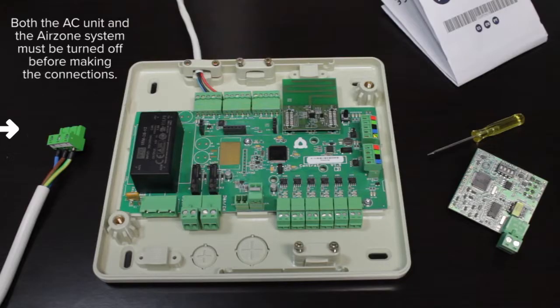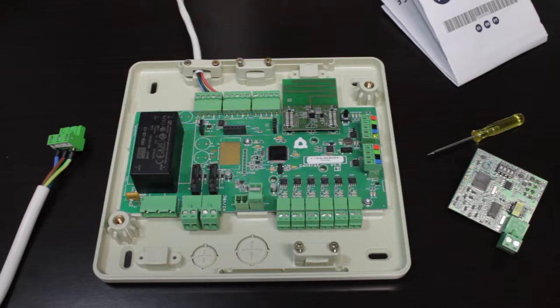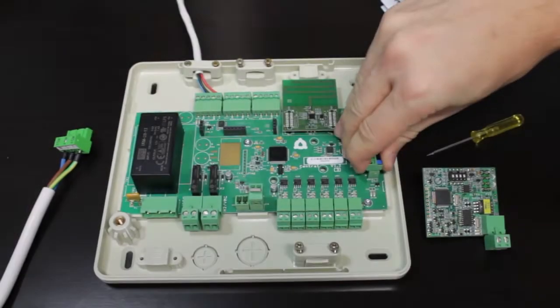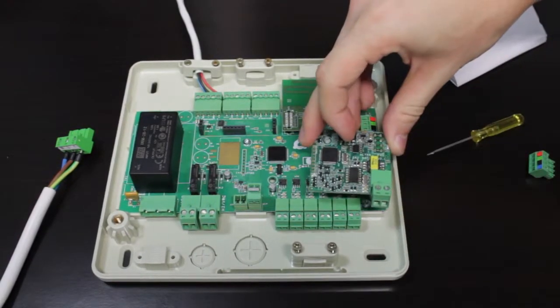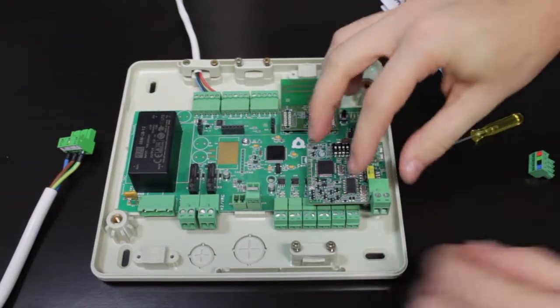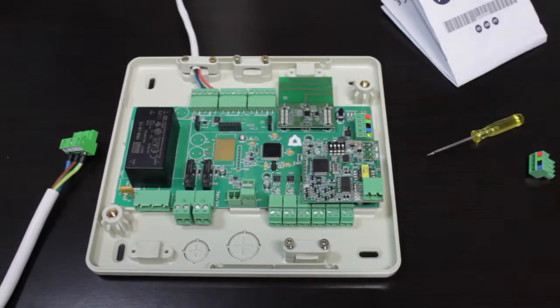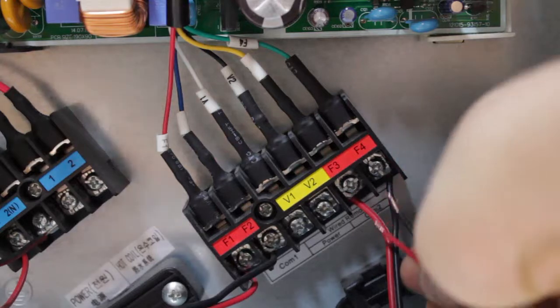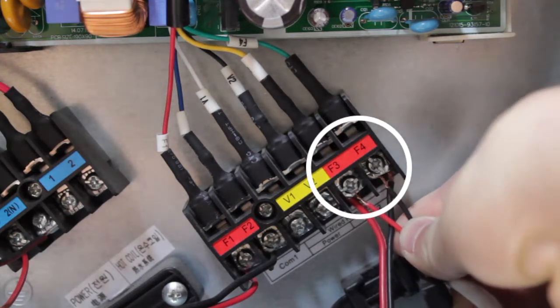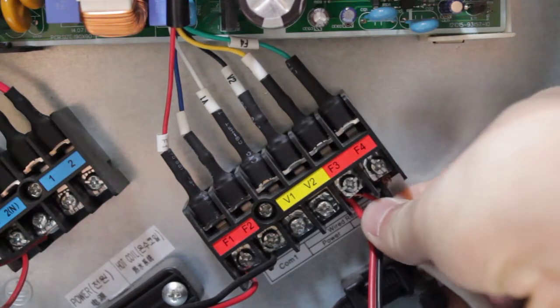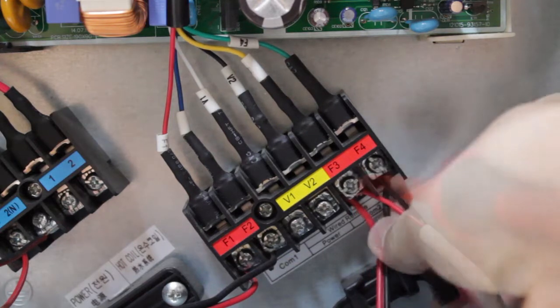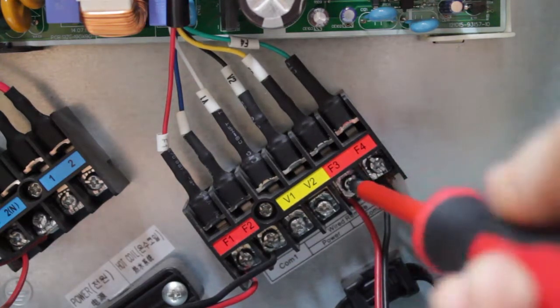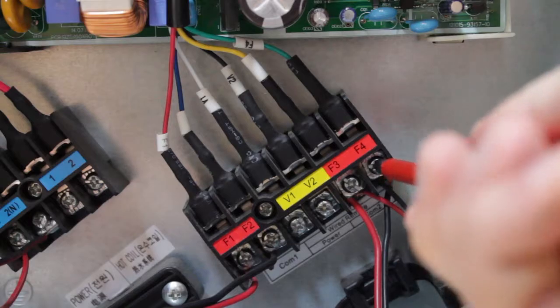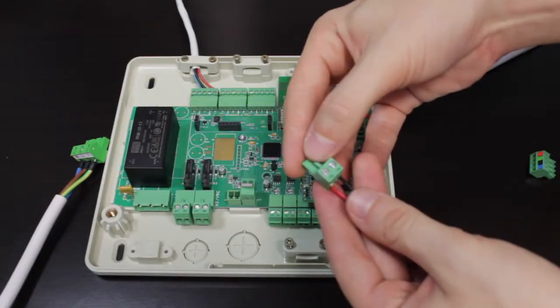Turn off the power to both your Airzone system and your Samsung AC unit before making the connections. Connect the gateway to the AC unit port on the Airzone main control board and secure it using the fixing post supplied. Locate the F3, F4 connector on the Samsung AC unit electronics where the thermostat is connected, and connect the Airzone gateway to this port using a two-wired shielded cable.